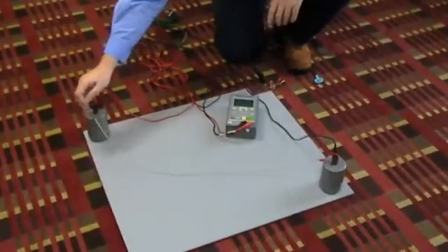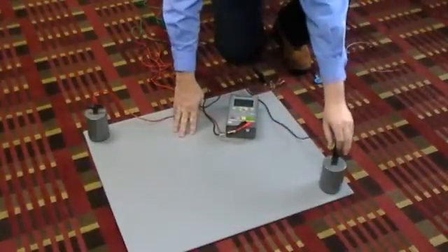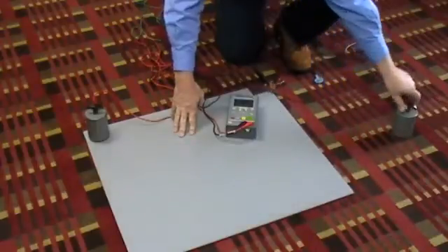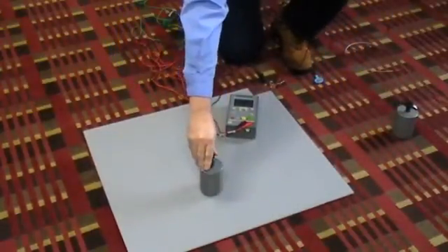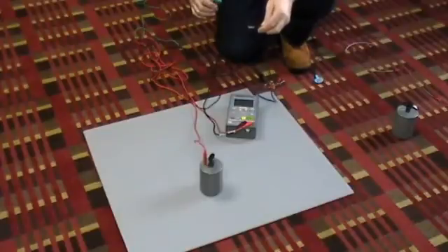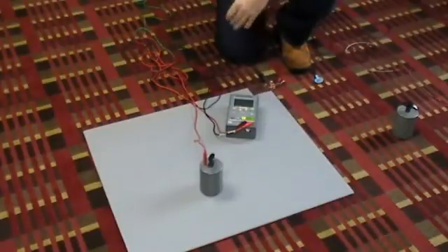We're going to disconnect the three-foot measuring cable and disconnect the negative lead from the five-pound weight. We'll move the positive lead to an accessible point on the floor and apply the second negative lead to ground, known ground.